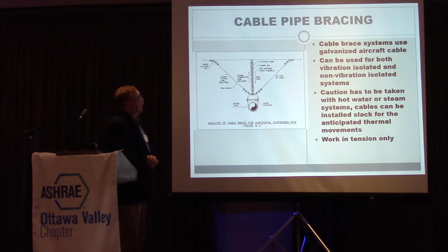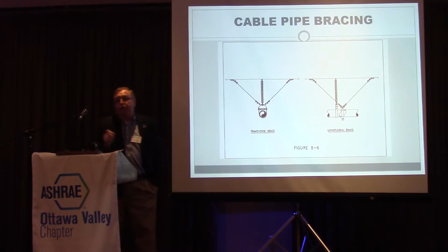Now, longitudinal bracing, which is in the length of the pipe - if we were to use a system like this on a longitudinal brace, you're really just bracing the clevis hanger itself. Because this little bit of movement within the clevis is not a problem for transverse. In longitudinal, the pipe would just slide in and out of the clevis and wouldn't do you any good. So you actually have to brace the clevis. You brace the longitudinal brace behind the clevis, and we usually use a pipe clamp - put a pipe clamp right behind it, then go off that pipe clamp so you're hooked onto the pipe itself. Now the pipe won't be sliding back and forth.